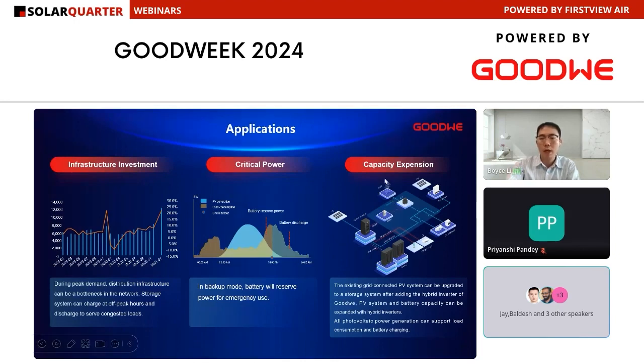We have both DC coupling inverters and AC coupling inverters. For DC coupling inverters, it's very easy to do capacity extension, because if there is already an existing PV system, if we install DC coupling inverters, we can also extend the PV capacity.